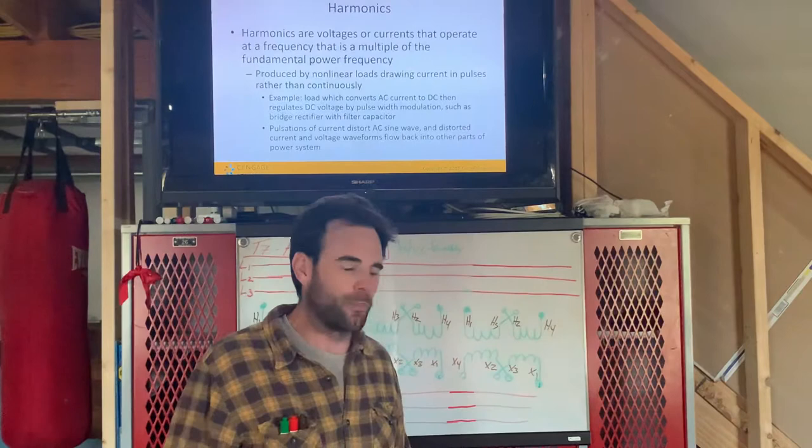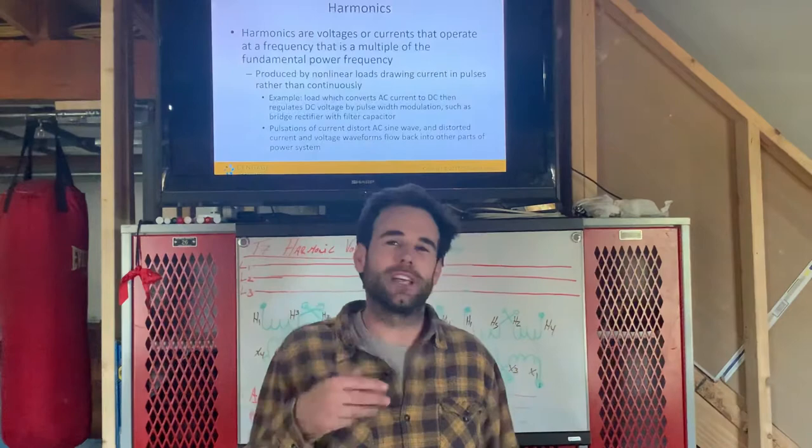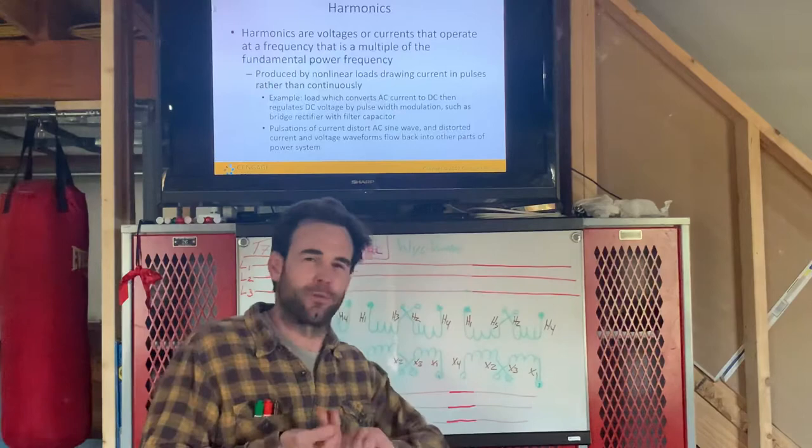Harmonics, when they first started discovering them, in the 80s or so, when the personal computer came out, and people would just start plugging personal computers into outlets. The problem is they didn't realize the effect that they were causing. Some of the problems they were causing was nuisance tripping on breakers, or the breaker not tripping at all when it should.